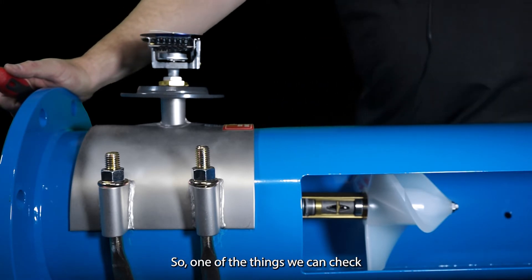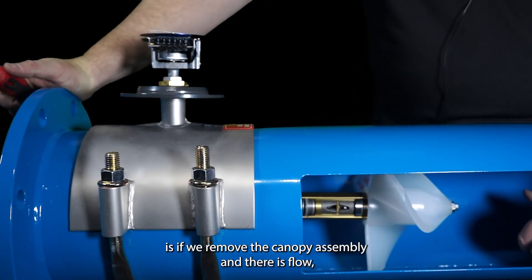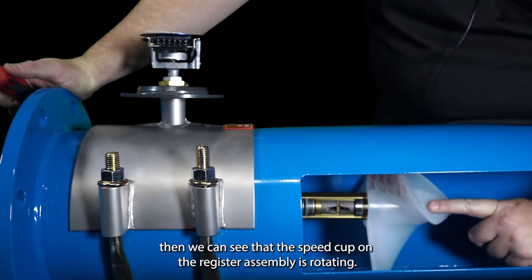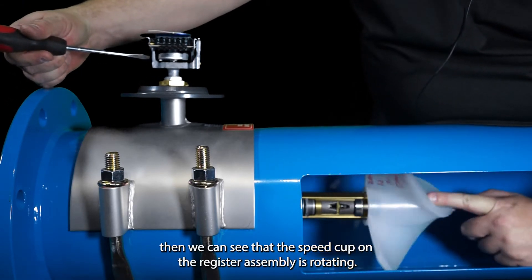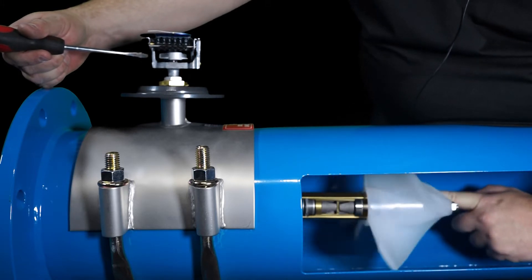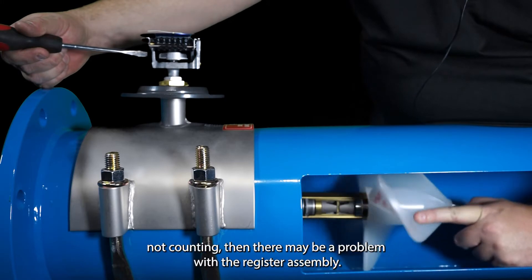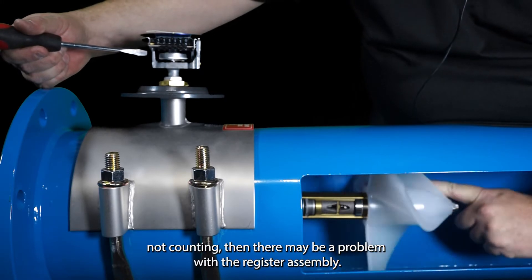So one of the things we can check is if we remove the canopy assembly and there is flow, then we can see that the speed cup on the register assembly is rotating. In that case if your needle is not reacting or your totalizer is not counting then there may be a problem with the register assembly.